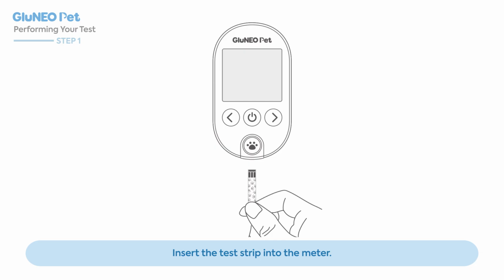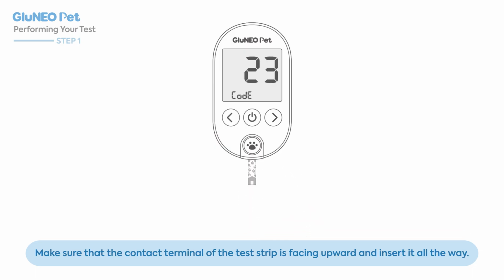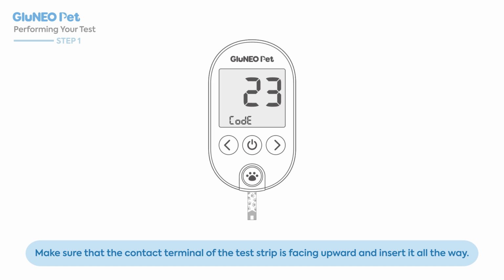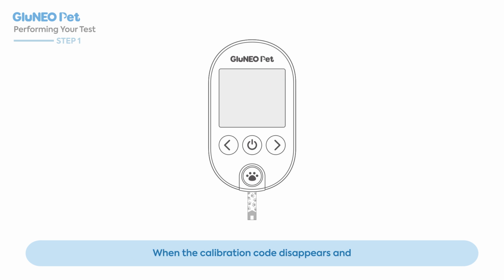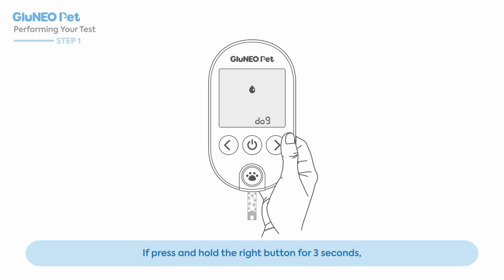Performing your test. Insert the test strip into the meter. Make sure that the contact terminal of the test strip is facing upward and insert it all the way. When the test strip is inserted, the screen turns on and the calibration code is displayed. Make sure that the calibration code displayed on the screen matches the calibration code printed on the bottle of the test strip. When the calibration code disappears and the blood injection symbol flashes, species is displayed. If you press and hold the right button for 3 seconds, the species to be tested will change with a beep sound. Then, collect blood from the test site.